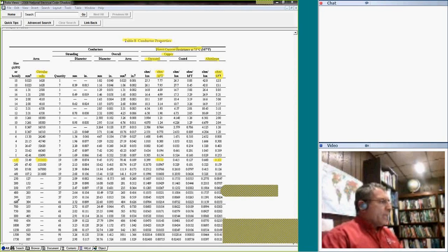Now, guys ask me, Chad, if I have 600 kcmil, what's the circular mil for 600 kcmil? The circular mil for 600 kcmil is not given, right? Because it's actually 600,000. K is 1,000. I can't believe people ask, I can't find the circular mil for 600 kcmil. Well, 600 kcmil, buddy, is 600,000 circular mil. The same thing for all these. They don't write them here because it's redundant, right? 400,000, 500,000, and so forth.